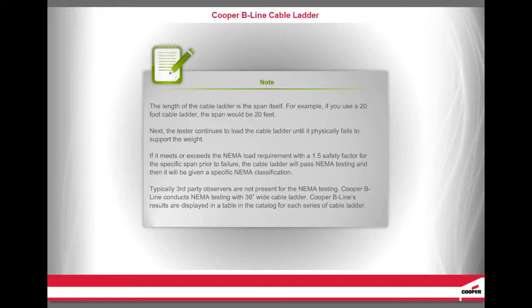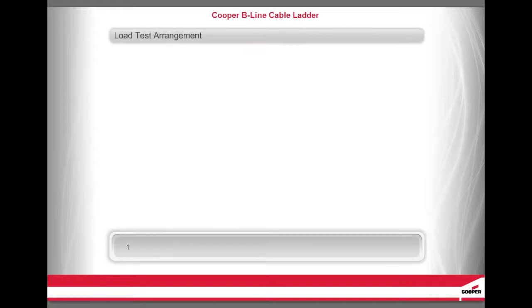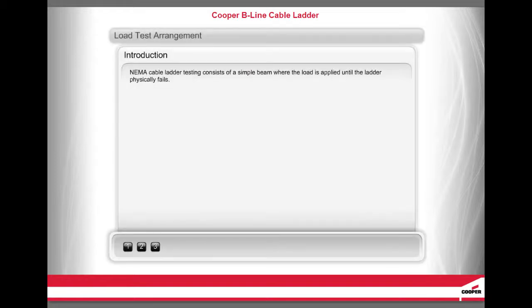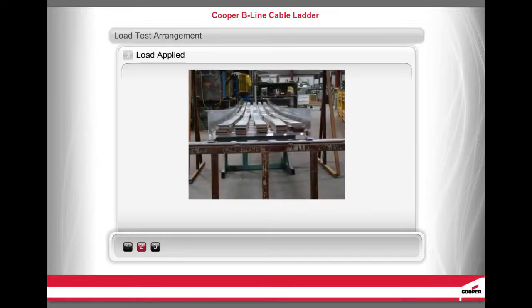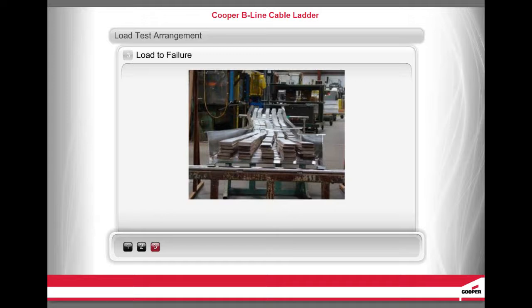Typically, third-party observers are not present for the NEMA testing. Cooper B-Line conducts NEMA testing with 36-inch wide cable ladder, and the results are displayed in a table in the catalog for each series of cable ladder. NEMA cable ladder testing consists of a simple beam where the load is applied until the ladder physically fails: simple beam, load applied, load to failure.